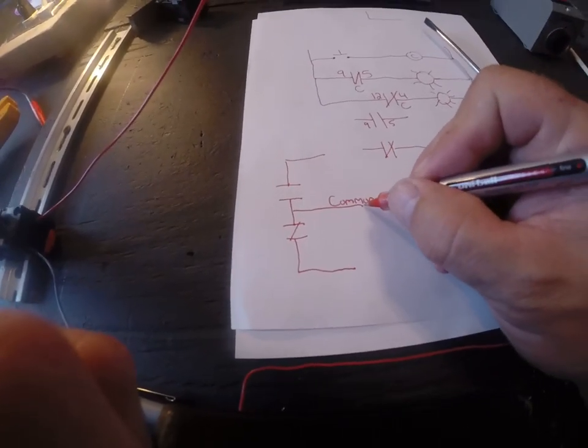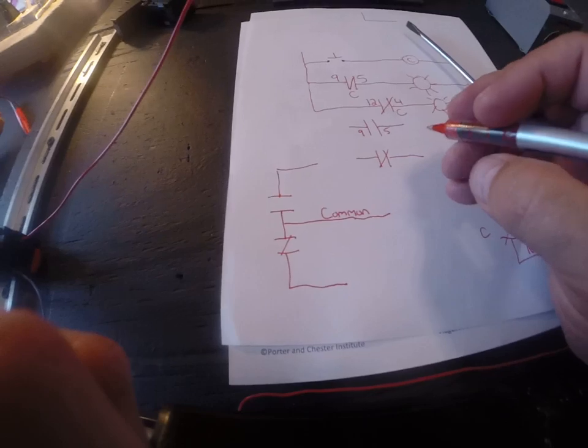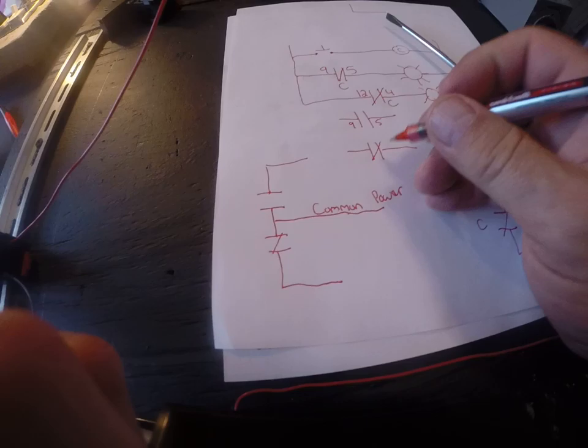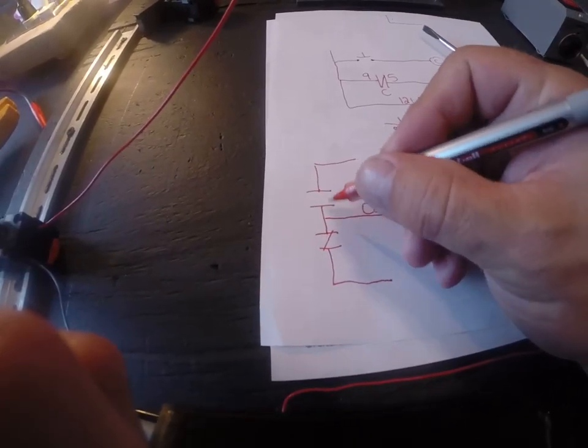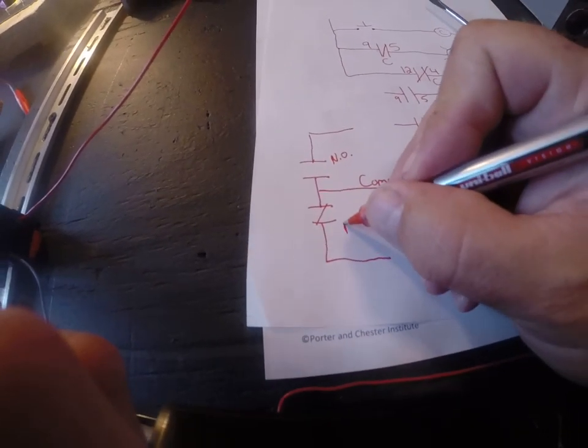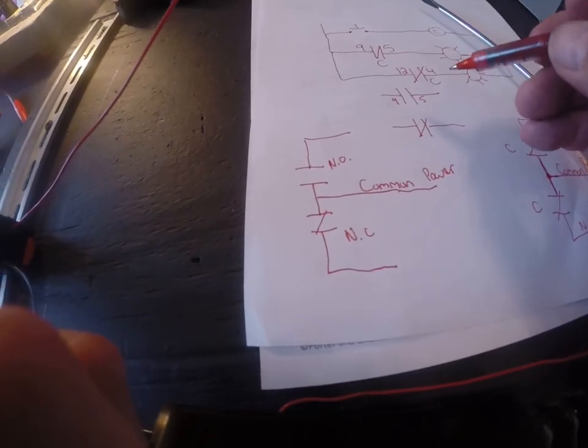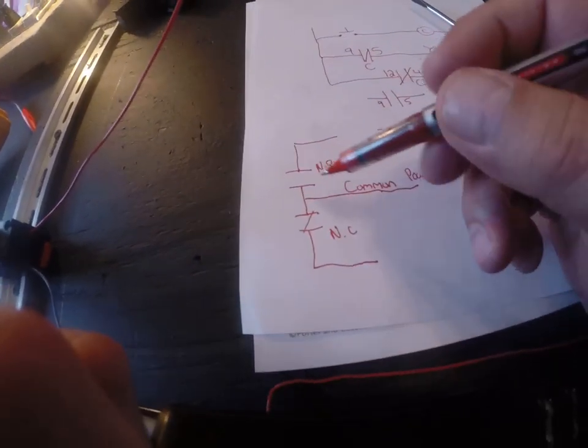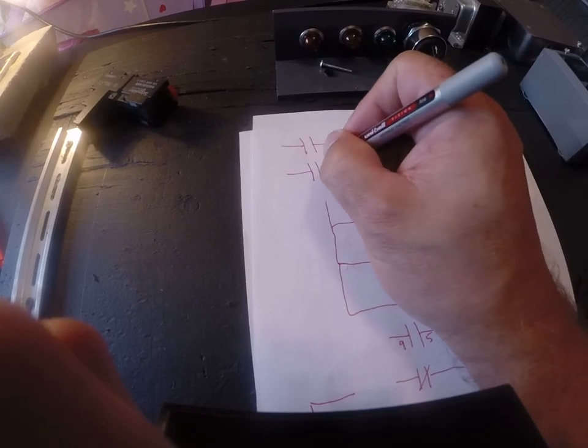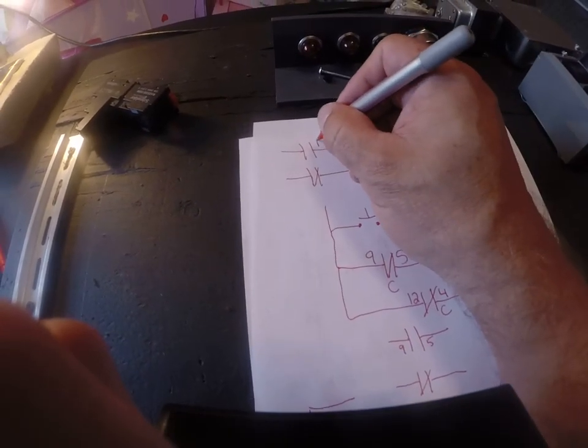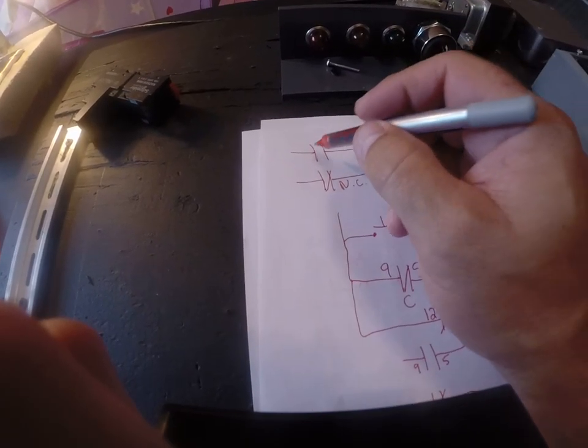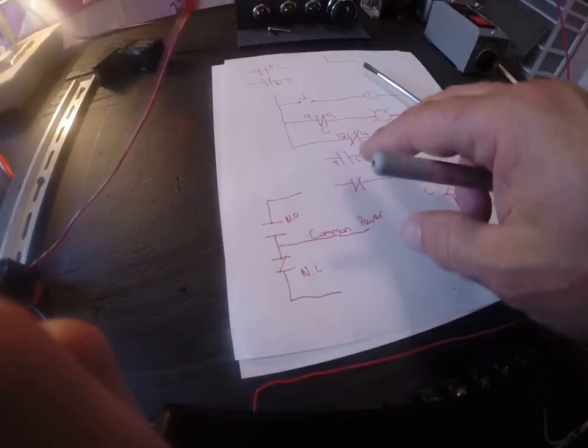So what you do with this common is entirely up to you as far as how it works with your diagram. But usually there's power that's put here. And then because this is common it's in common with this normally open and this normally closed contact. We use these contacts a lot with relays and you have to understand that this symbol is normally closed. This one's normally open. And how these are labeled is very important to how the circuit works.